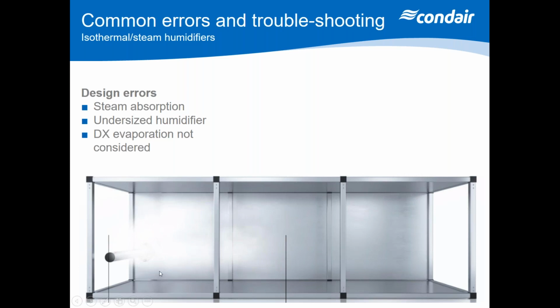And what's going to happen is it's going to either click the high limit and turn the humidifier off and go into the security open loop circuit, or it could be a modulating signal which will just ramp the humidifier back. But what's going to happen is you're not going to get the humidity in the space where you need it, because the sensor's still sensing at this high level here. So normally what we recommend is that the sensor be mounted at 5 times the absorption distance to give you the correct controllability.